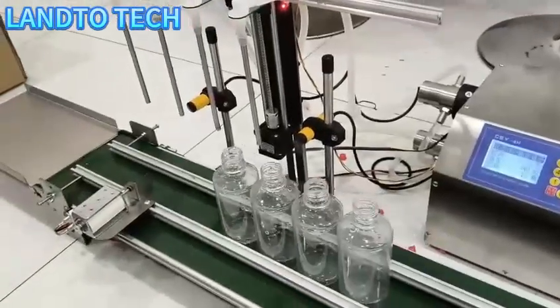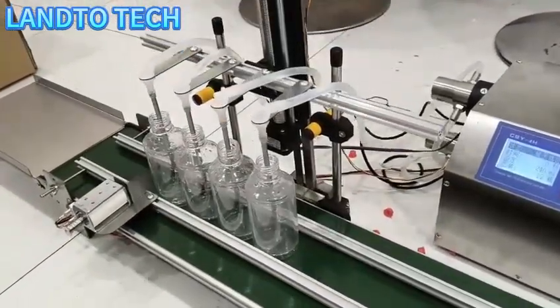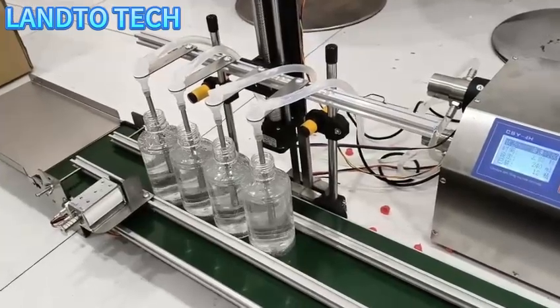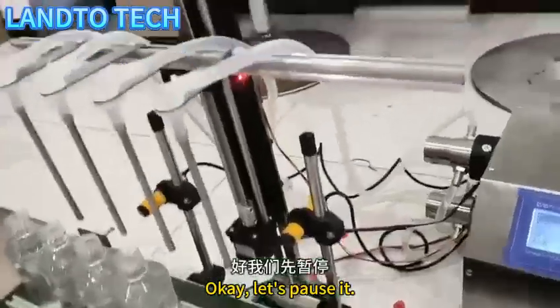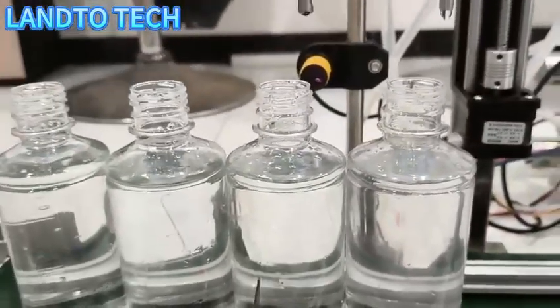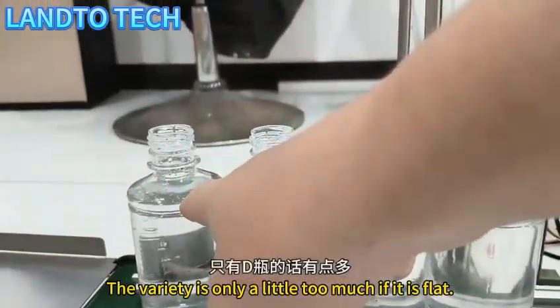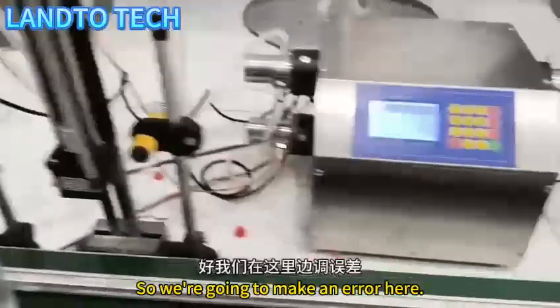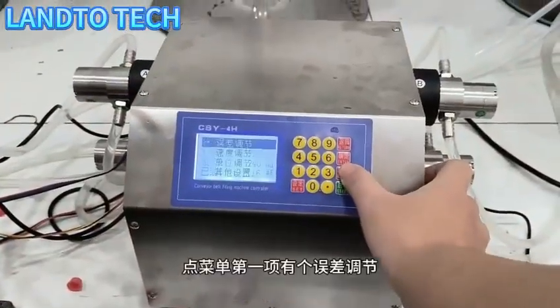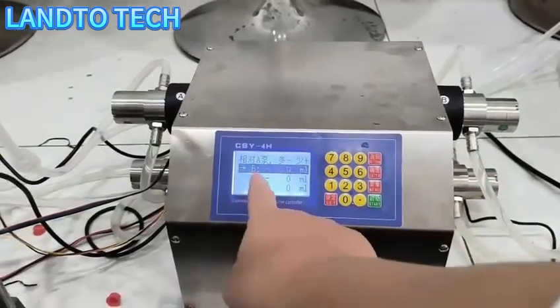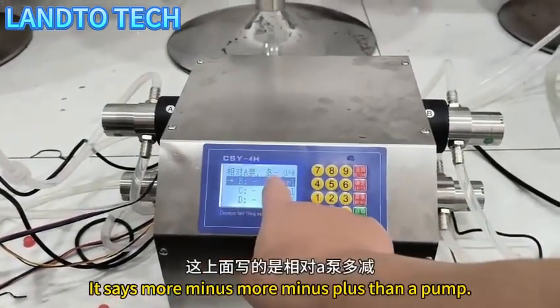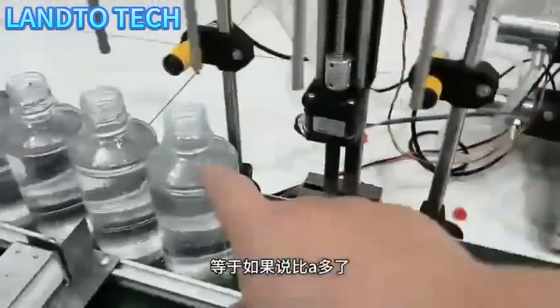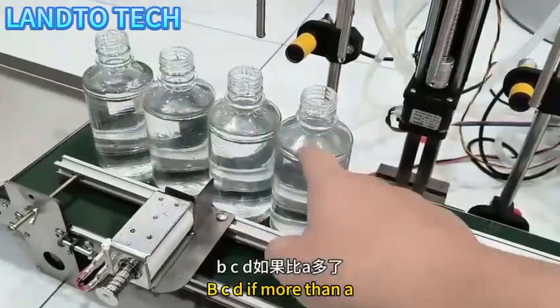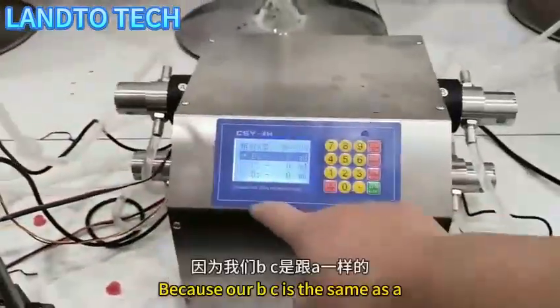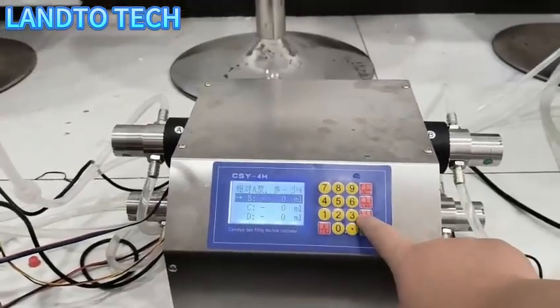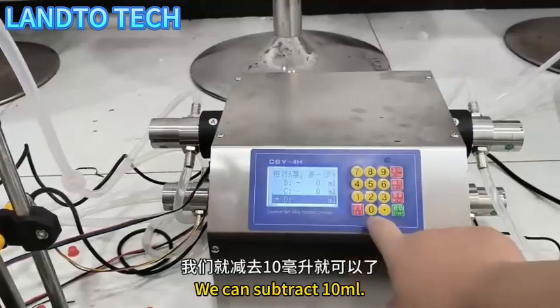Start. Okay, let's pause it. Take a look. Now ABC are the same. Only D is a little too much, so we're going to make an error adjustment here. Click on the menu. The first item has an error adjustment. It says more minus, less plus, per pump. If it is a lot more than A, for B, C, D, if more than A, then you reduce. If it is less than A, you add. Because B and C are the same as A, only D is too much. We can subtract 10 milliliters.